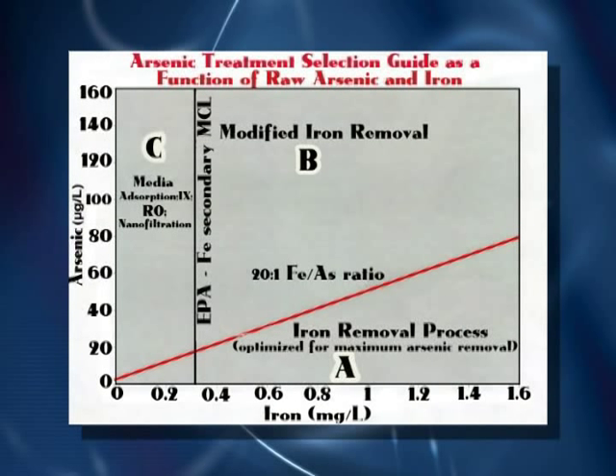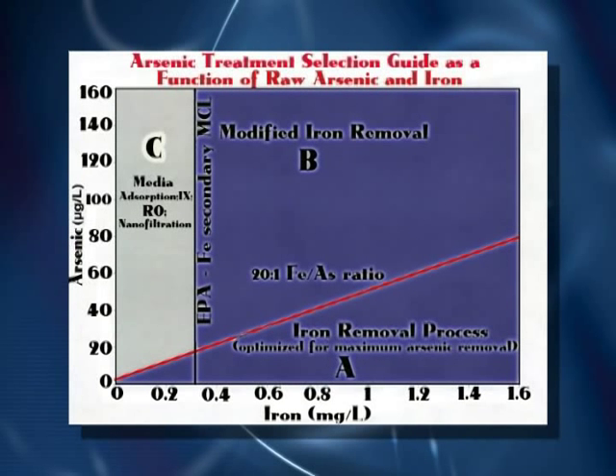Iron plays a unique role in the removal of arsenic, and the presence of iron in the source water will play a big role in treatment process selection. On the chart, the horizontal axis represents iron concentration in the source water and the vertical axis reflects arsenic concentration. The vertical line at 0.3 milligrams per liter iron is the EPA recommended secondary standard. Using the 20-to-1 iron-to-arsenic mass ratio, you can create a graph with three zones to assist in identifying arsenic treatment processes.